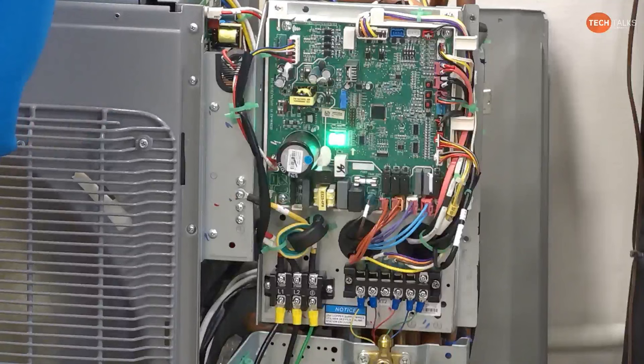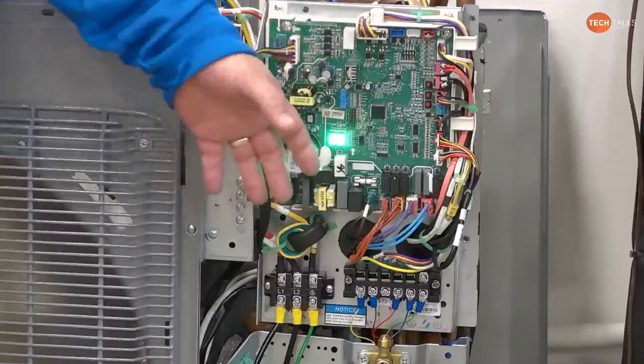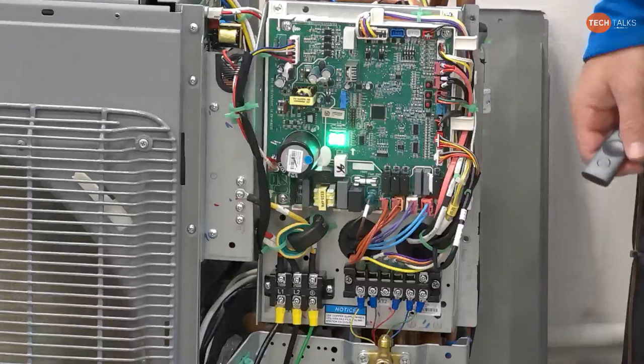Right. This is the kind of stuff we've learned from guys calling in and actually troubleshooting the unit. At least that's been my experience with it. Normally when the motor fails, it doesn't take the board with it. It might blow the fuse, but it doesn't wipe out the board. And that fuse is actually replaceable on this one.